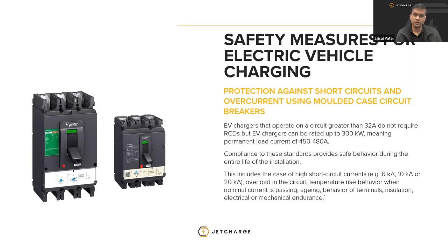Now, again, because every charger is different, read the manufacturer's manual, because, for example, the Tritium, one of the more popular EV DC chargers here in Australia, typically does not require a neutral because it only has a 3-core plus earth, which essentially means if you put in an RCD with an MCCB, it won't operate because the RCD will prevent it from running. So it's always important to check with the manufacturers before you specify any systems. Next slide.